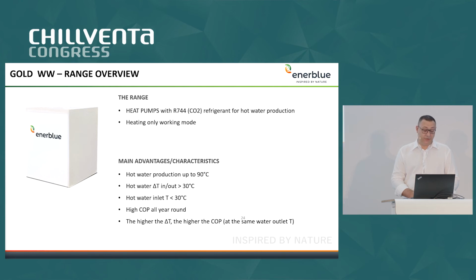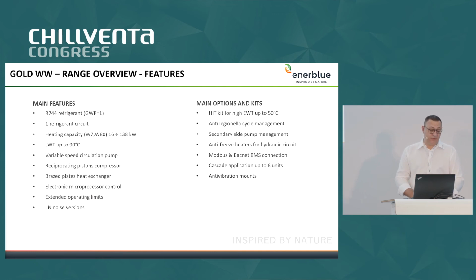Hot water inlet temperature maximum 30 degrees. But also in this case, we can have the HIT option that allows to work with inlet water temperature up to 55 degrees. In terms of features, also in this case, we have the circulation pump variable speed already on board. Also in this case, all the units are one refrigerant circuit with a reciprocating pistons compressor and plate heat exchanger. Controller and the operating limits are more or less the same we saw for the cool recovery version. And the low noise version is always included on the water-to-water units.